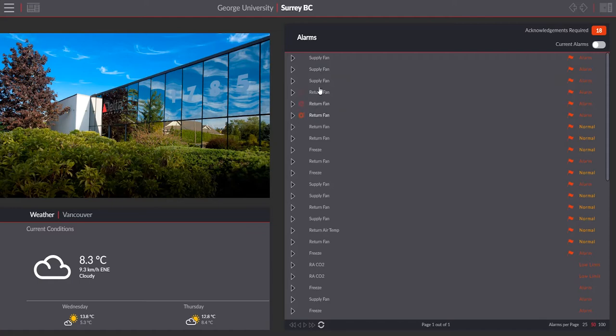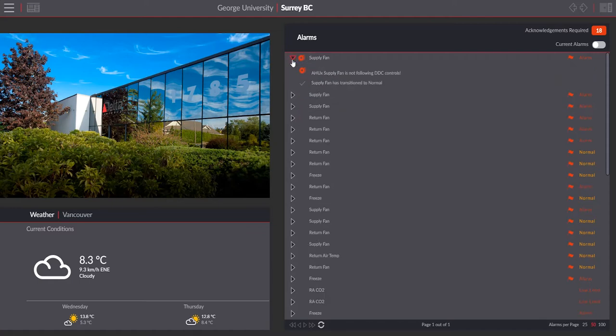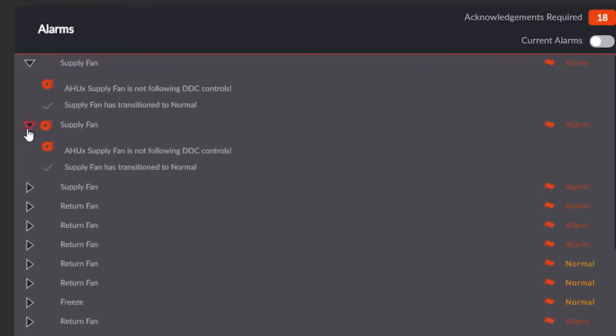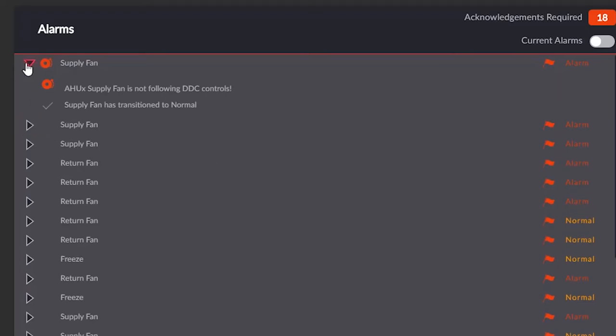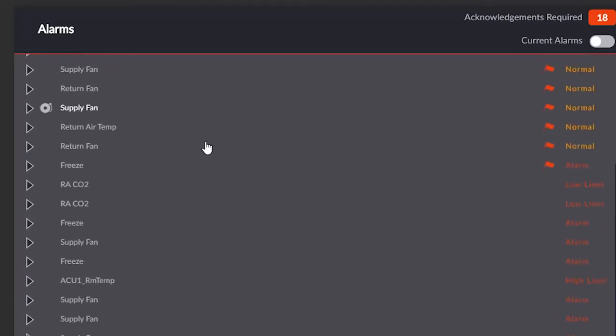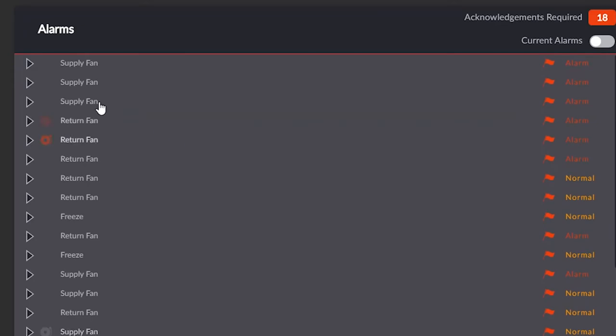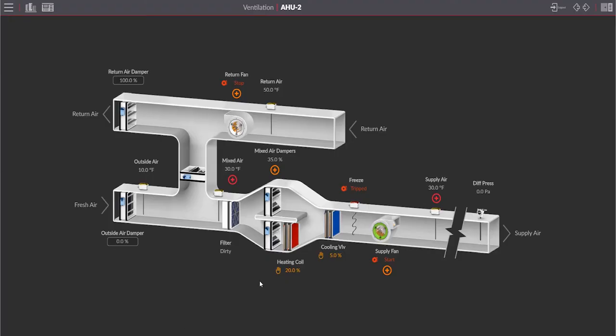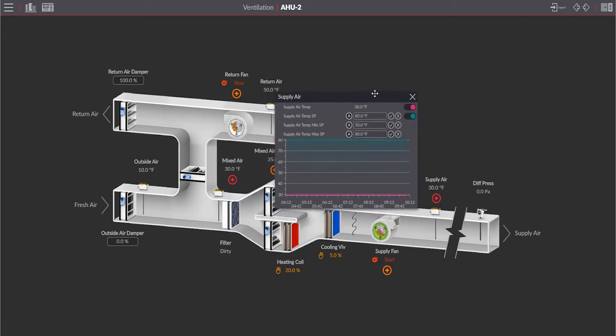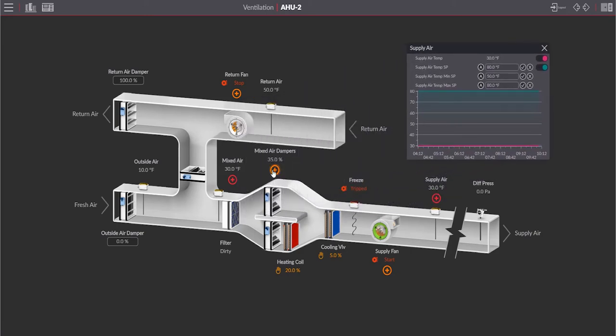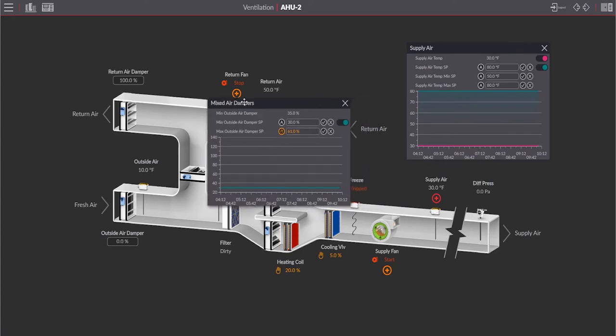Now to show you some of the symbols and tools that can be used with this template. There is a pre-made alarm console that auto-generates active alarms that are currently ongoing on your site. You have the ability to acknowledge your alarms directly from the graphic — you do not have to navigate to a different part of IntelliWeb to do this. Another notable one is called data information. All you need to do is assign an object ID reference to the symbol, and it proceeds to find all associated trends and auto-generates a nice-looking table. You can even have multiple pop-ups at the same time and move them around.